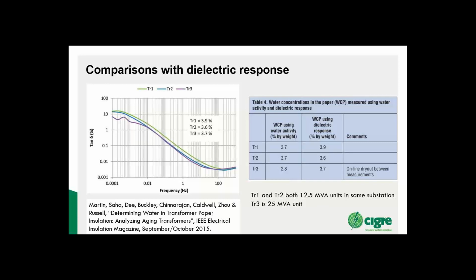Now these are some midlife transformers which we were looking at, and it was the same there again. We have our T1 and T2 within the same substation. They're the same transformer, same age, same type, and we got very, very close to the dielectric response, which we thought was great. Now TR3 in this had actually undergone a dry out process. So, well, we're not going to expect the water content to be the same, obviously, because we've dried the transformer out.